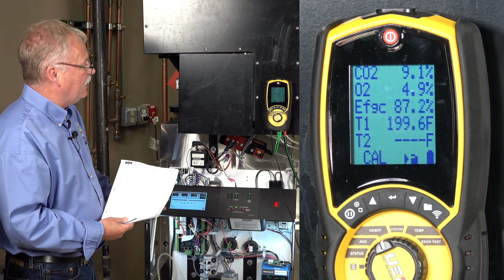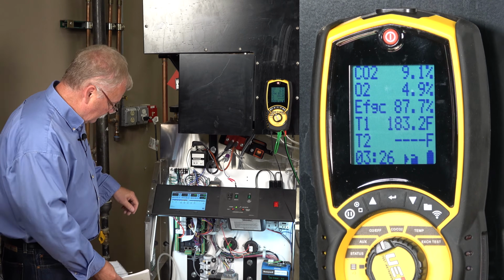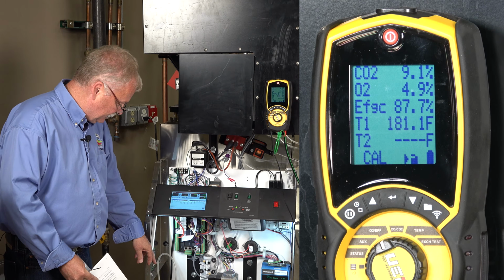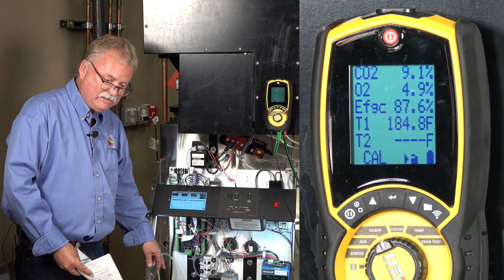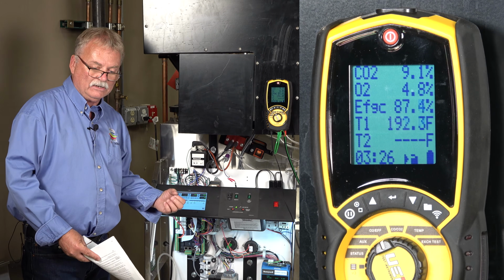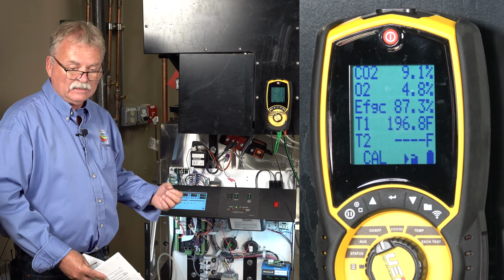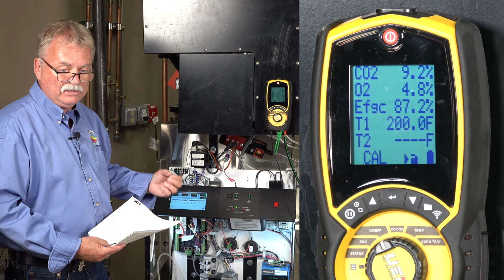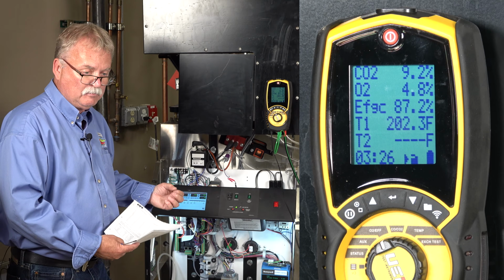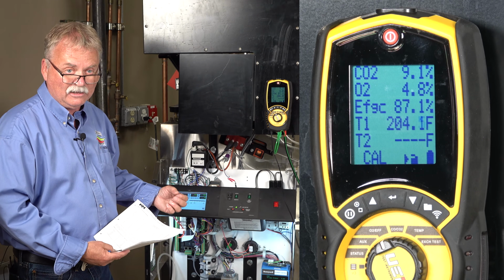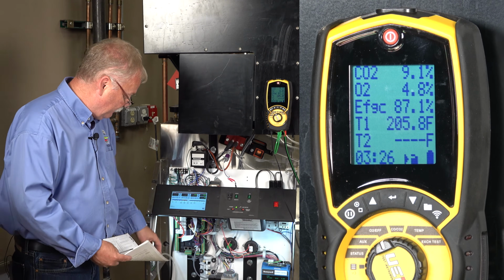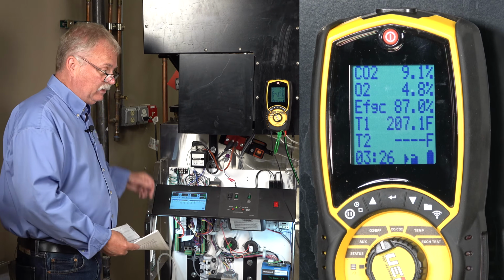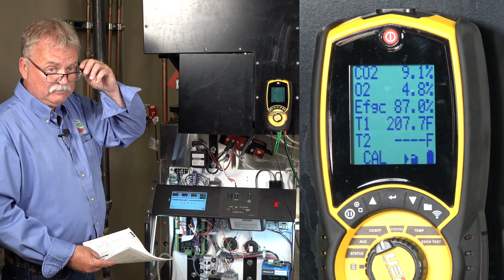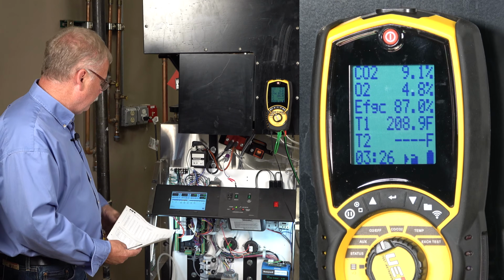Okay, so we seem to be about 9% there. My gas on high efficiency has dropped about 5.9. That means it went from about a 7 to about a 6. That's well within the range of this manufacturer. Like I said, this boiler can fire down to 3 inches of water column. Again, I have no way of controlling that because I am limited to what the city gives me on this job. All right?